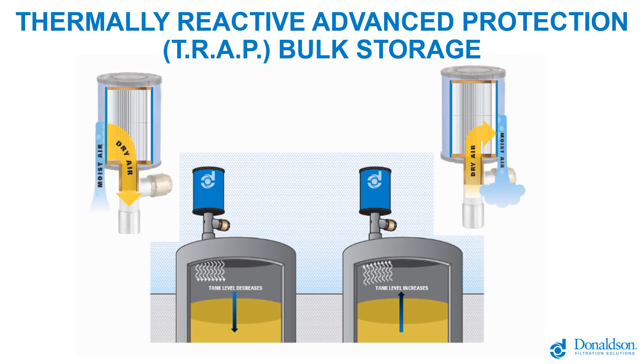Here we'll take a look at a TRAP breather applied to bulk tank filtration — same exact technology, just a larger format. On the left, the bulk tank level is decreasing as you dispense fluids into equipment. As air is drawn into the bulk tank to replace that fluid, it's cleaned by the TRAP breather, stripped of moisture and particulate down to three microns. On the right, the tank level increases as you receive a delivery, shrinking the headspace and pushing air back out through the TRAP breather, regenerating it and pushing moisture and particulate back out of the media.